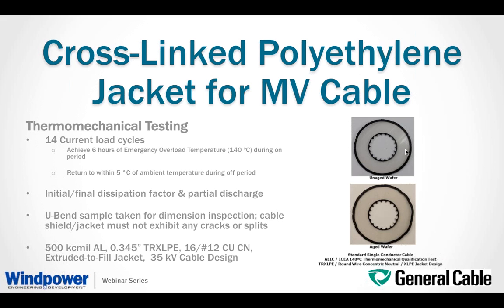So the test protocol consists of 14 current load cycles. During the 6-hour on period, the cable reached the emergency overload temperature of 140 degrees C for a 105 rated cable, and then returned to within 5 degrees C of ambient temperature during the off period. Then you measure the initial and final dissipation factor, and partial discharge testing is completed. Then dimensions are reviewed from a sample taken from the U-bend, and the cable shields and jacket are inspected. They must not exhibit any cracks or splits.